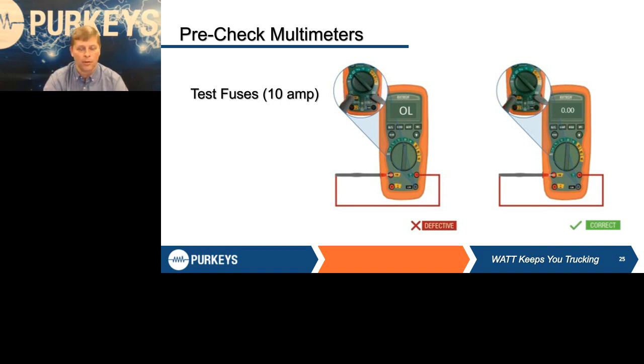But before you use it, just like we talked about before about pre-checks, you want to make sure your amp meter is working properly. What generally happens is you loan your meter to one of your buddies. He tries to use it for the amp function, forgets to move his leads back, puts it across the battery, and you're out $12 to go buy a new fuse. So before you try to use it, you've got to check that internal fuse.